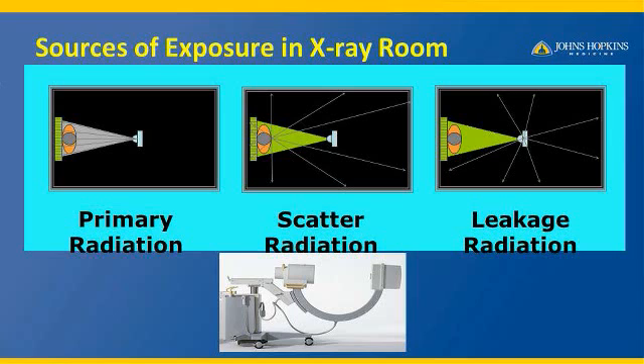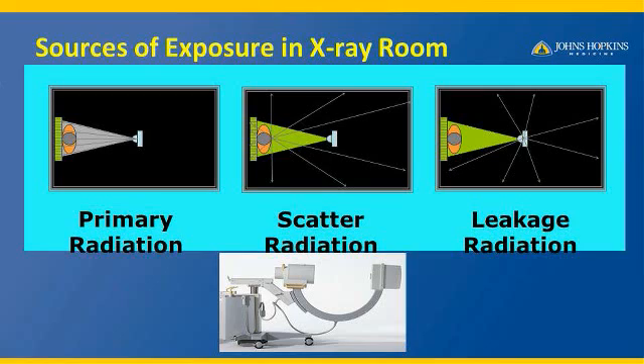In any x-ray room, there are three primary sources of radiation. The first is called primary radiation, which arises from the source and is confined to the size of the image receptor. The second source is scattered radiation, which arises from the patient. When x-rays pass through the patient, the patient actually scatters radiation in all directions, and this is one of the sources which we need to protect ourselves from if we are inside an imaging room.